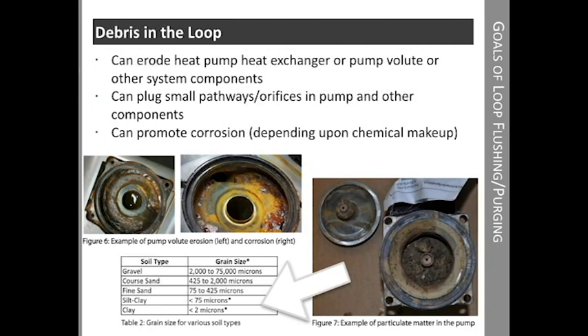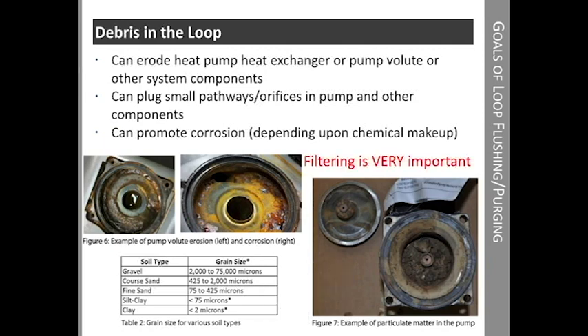Debris can be very fine. As you can see from the chart, fine sand, silt, and clay can be less than 100 microns. In fact, clay can be as small as 2 microns. When flushing the system, we typically use a 100 micron filter, which catches larger particles. However, once the system is purged of air, additional filtering may be required. GeoFlow offers a 1 micron filter for additional removal of smaller particles. The 1 micron filter should not be used when purging air due to the high restriction. However, once air is purged from the system, it's a good idea to do some additional filtering with the 1 micron filter.